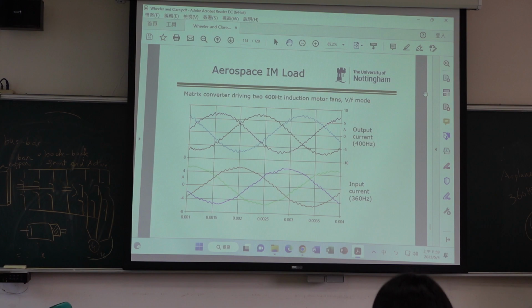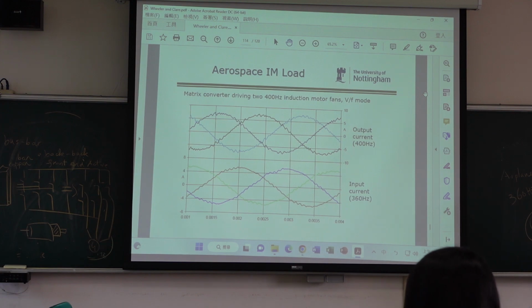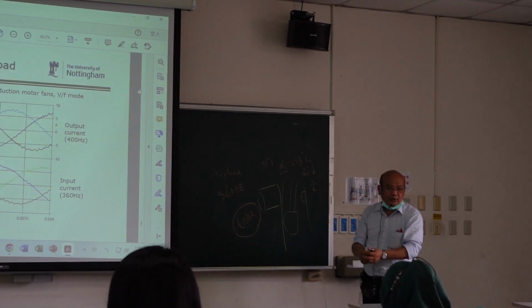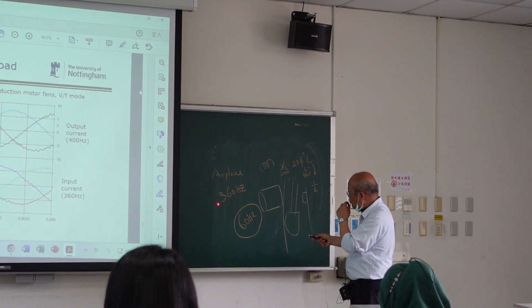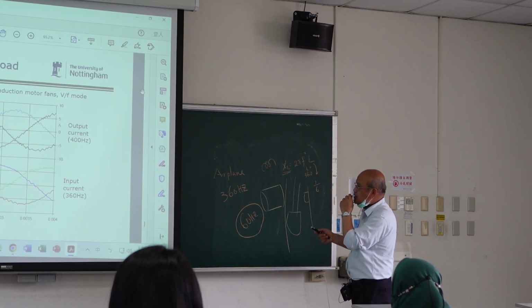The reason is you have an inductor. If your frequency is higher, say 360 Hz, which is 6 times higher, then for the same reactance, your inductor becomes 1/6 smaller. Your motor becomes smaller. The reason is your frequency is higher but your reactance stays the same, so your inductor becomes smaller. If you have a smaller inductor, then your motor size becomes smaller too. So this is the reason airplanes like to use 360 Hz, to make everything smaller.